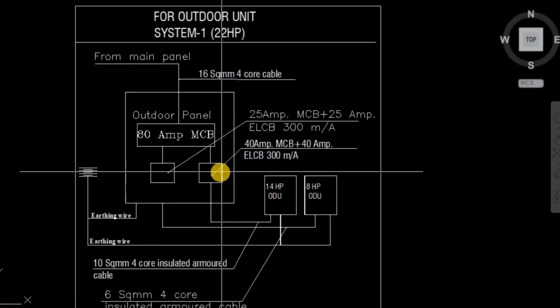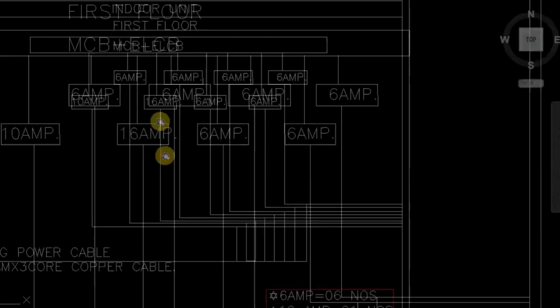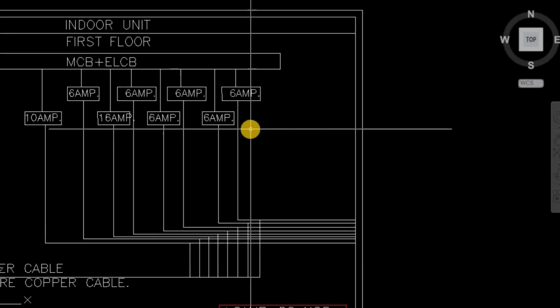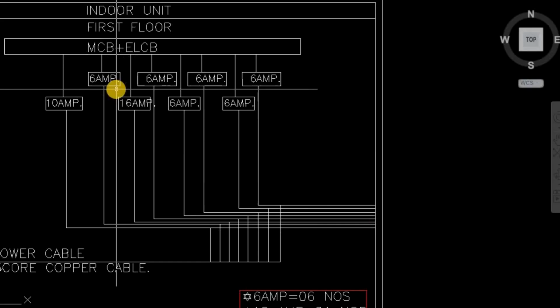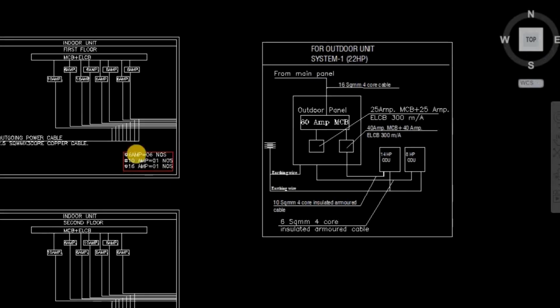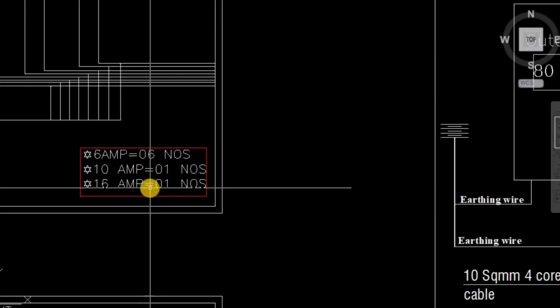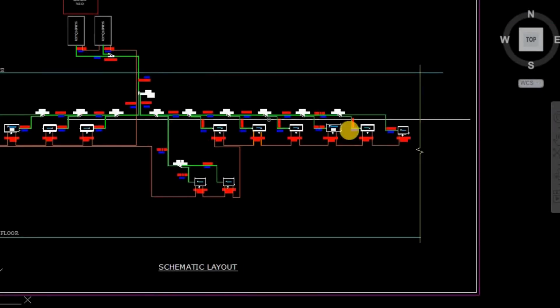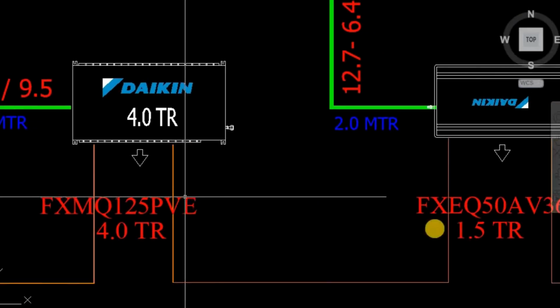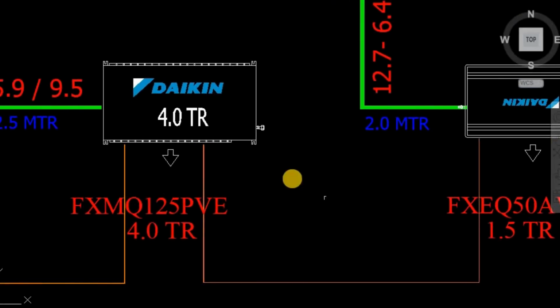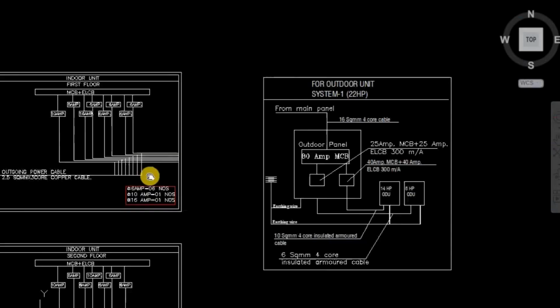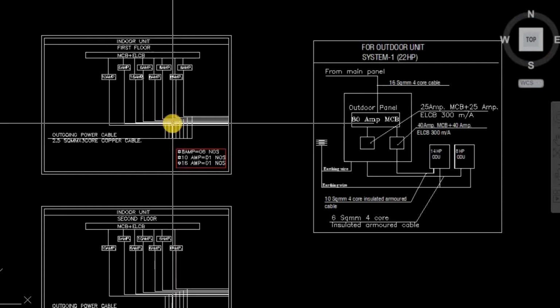And what are the, okay friends, these are the indoor units. You can see 6 ampere, 6 ampere. Most of the indoor units will be 6 ampere. If there is a large indoor unit, it will be 10 ampere. You can see this is 10 ampere, 6 ampere, 16 ampere also there. This depends upon the different type of unit. This you can see 50 and this is 125 for 4. So we are using 10 ampere unit also. Okay, hope you understand up to this one.